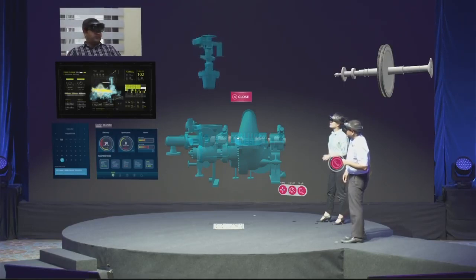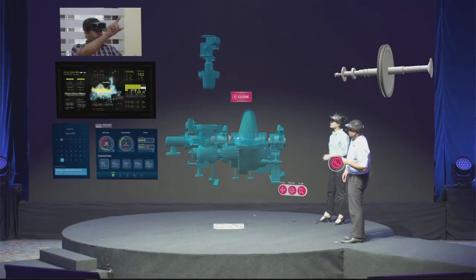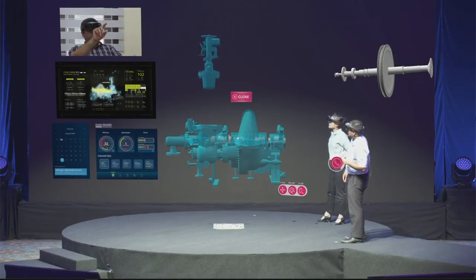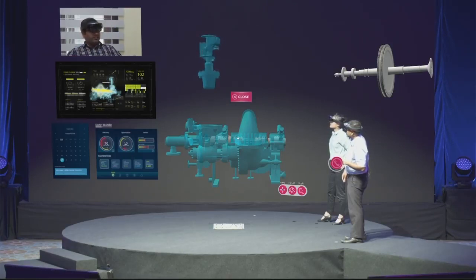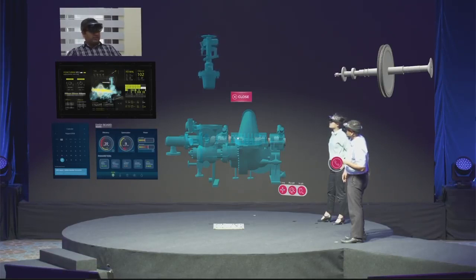Hi, Akil and Lina. It seems that we have quite a situation over here. Let me check the operating parameters and some historians. Well, there is indeed a pressure drop, but it's not sudden — it's decreasing gradually. Looking at this data, I'm pretty much sure there are some serious blade deposits. You would need to schedule an overhaul for her.